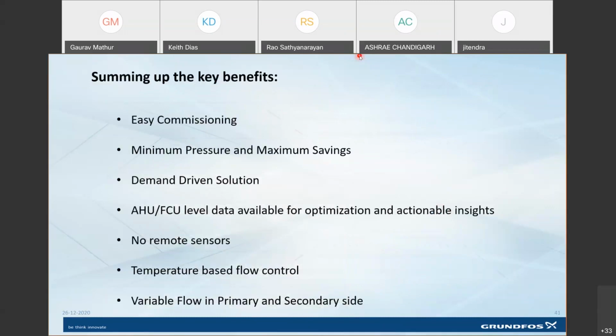The first thing, which is very important, and I would like to connect here with the initial point of digitalization, which we discussed: the easy commissioning and the host of data which is available for actionable insights. And that is the primary benefit which you get out of distributed pumping. The second is minimum pressure and maximum savings. We have discussed that the sizing of the pumps reduces, the pressure in the entire circuit reduces, which we have seen in the form of a hydraulic gradient diagram. And that essentially translates into savings.